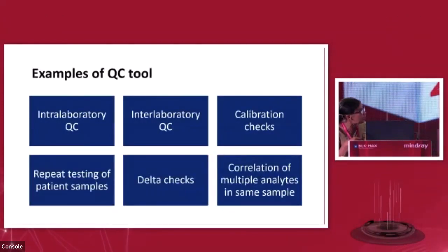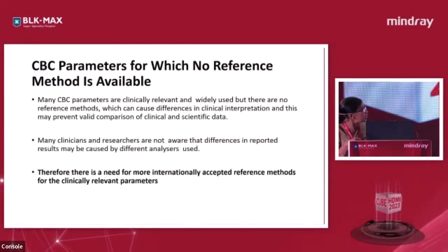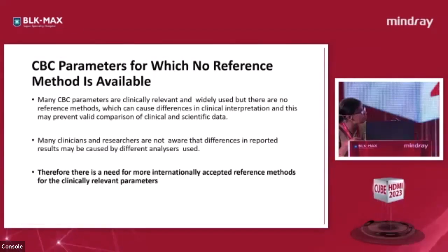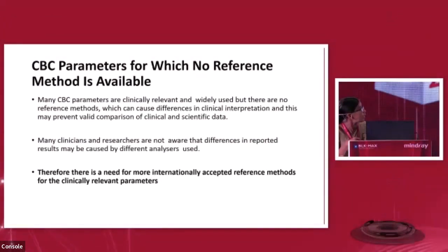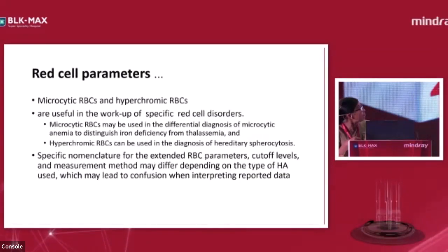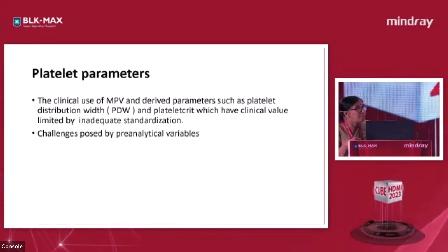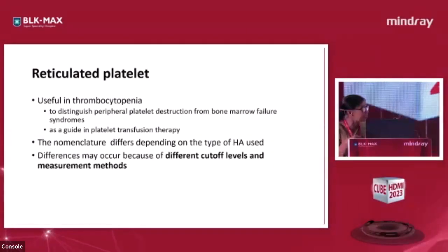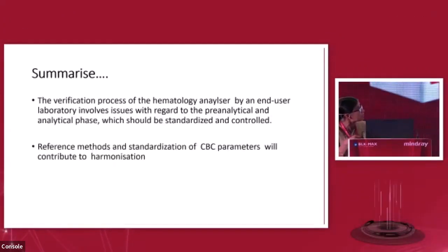So these are the various QC tools that we just spoke about. I would like to conclude this session by drawing your attention to certain important aspects. Not all CBC parameters that we use have reference methods, so that can pose a challenge. For MCV and other parameters, there is no reliable reference method. For platelet parameters, there are many pre-analytical variables that come into the picture, so that can be challenging.